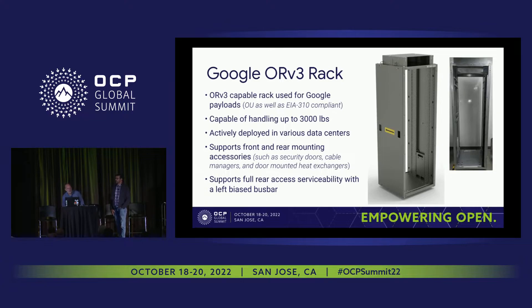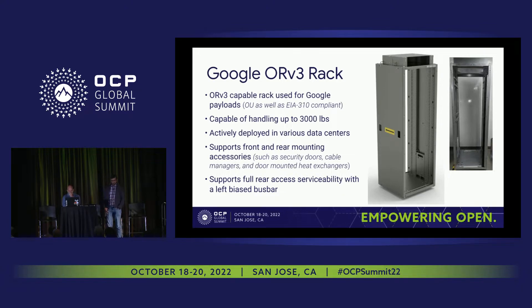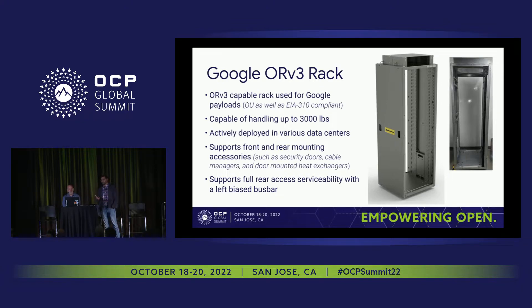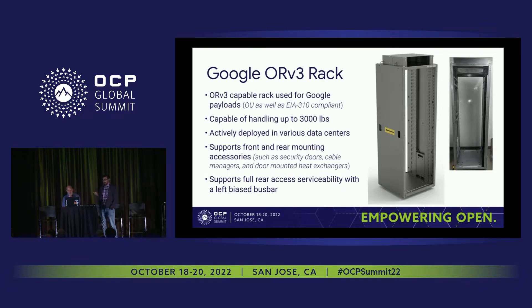At a high level, the Google OpenRack, as the base spec calls out, supports OCP and 19-inch payloads. We've been able to qualify it for up to 3,000 pounds of IT gear. It's currently being deployed — we've had a few quarters of deployment on it. We've been really leveraging the front and rear mounting features to develop a lot of modules to meet different data center requirements from security, cable management, containment, and so on. We're also finding a lot of serviceability benefits with the left bus bar position, which Loren will go into in a little bit.